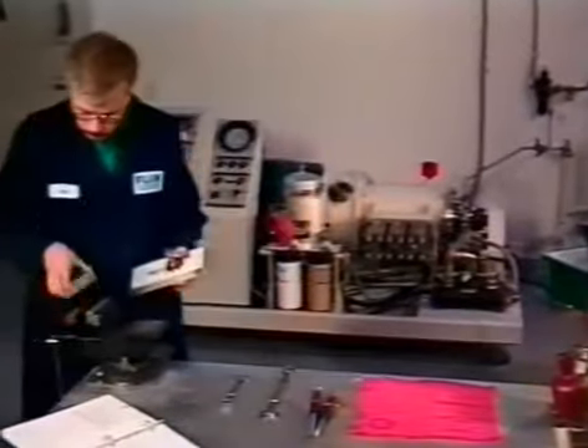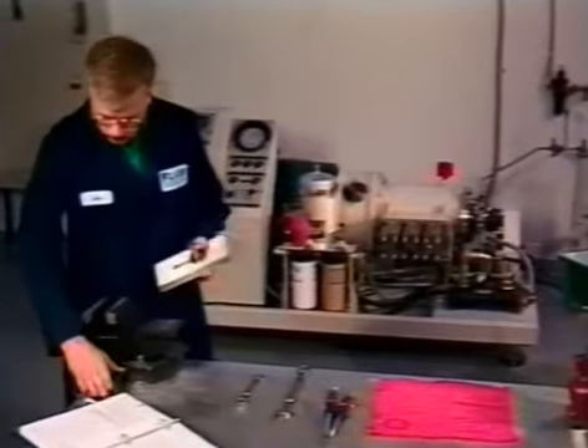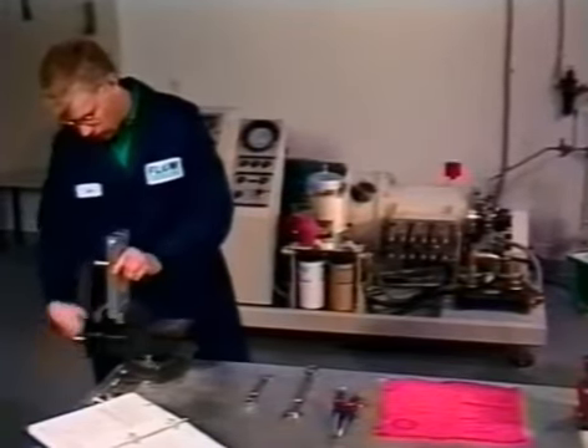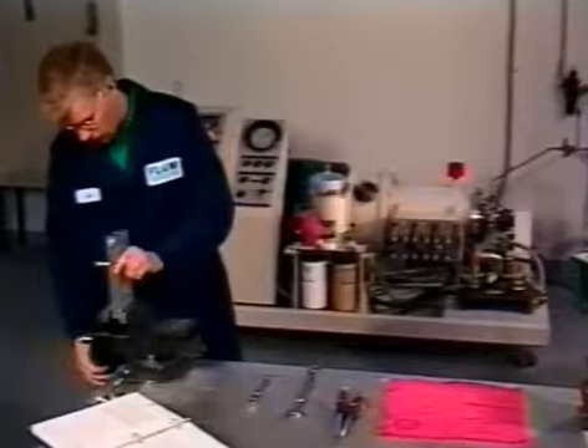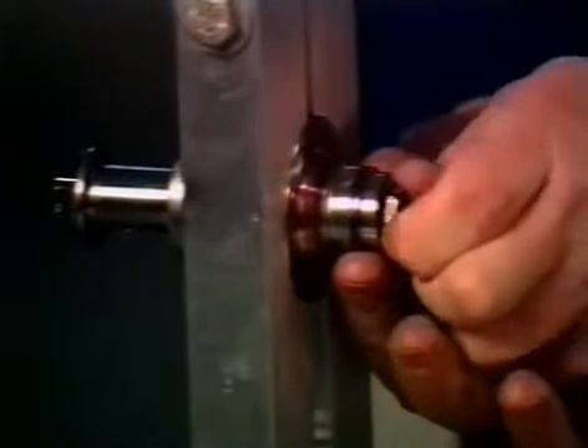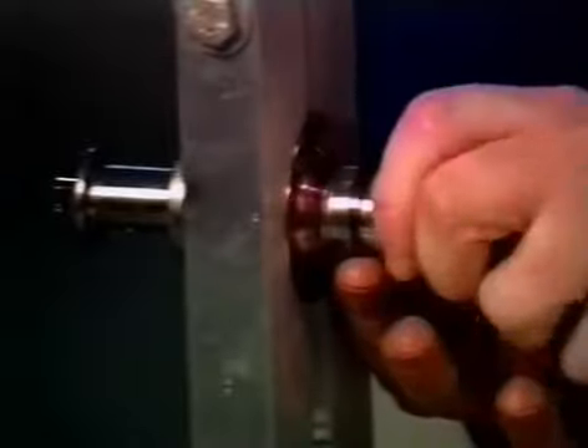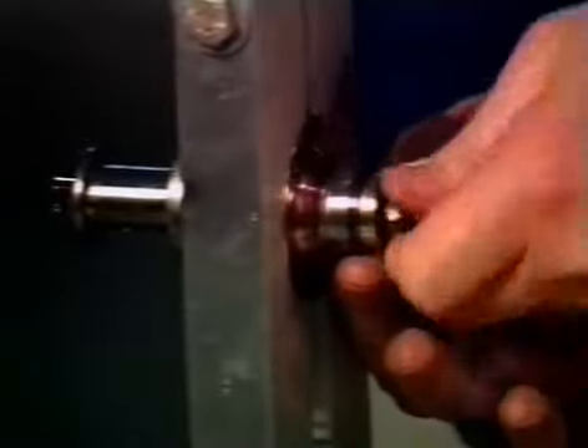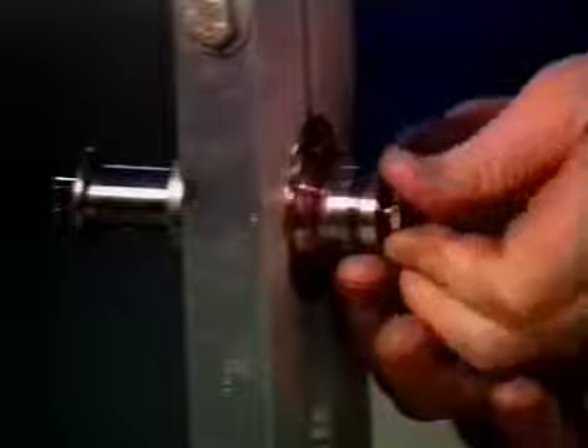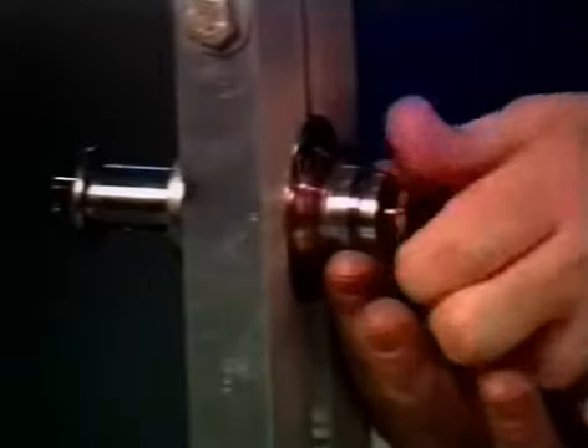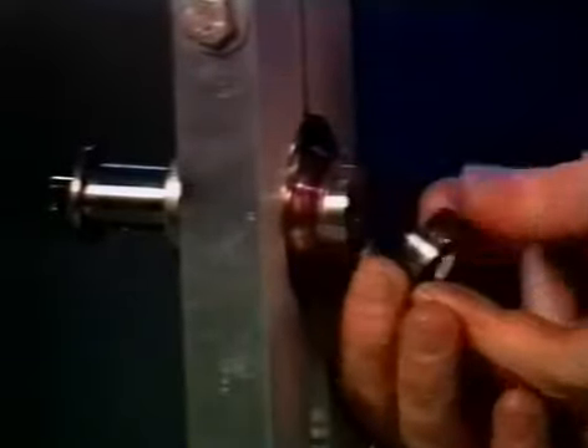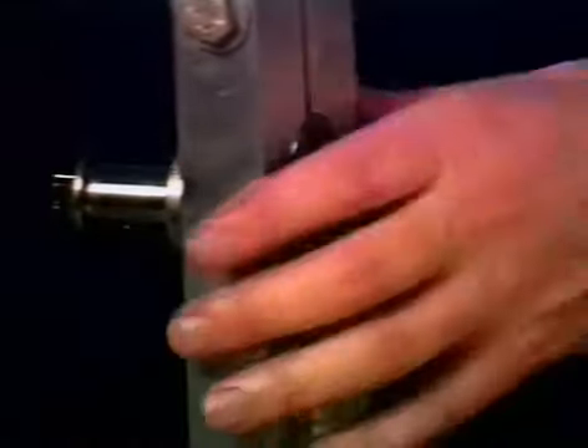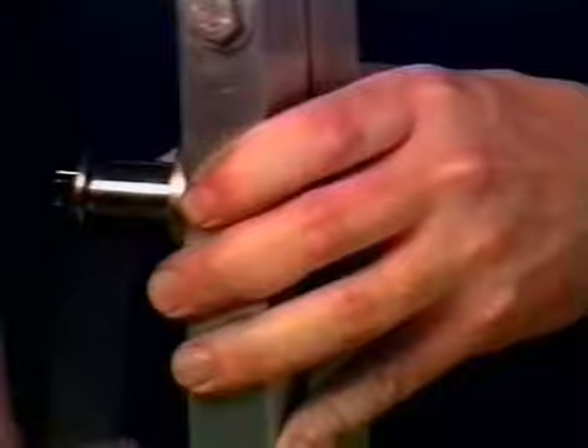Now place the clamp in a vise or hold the clamp by some other means. Remove the inlet poppet and the inlet seat assembly. If the check valve has failed, look for erosion, pitting, or other signs of wear between the poppet face and seat face, and between the seat and body. When you replace the inlet poppet and seat assembly, also replace the inlet screw.